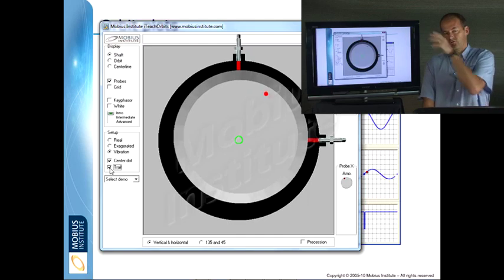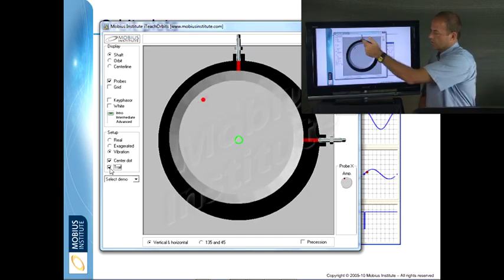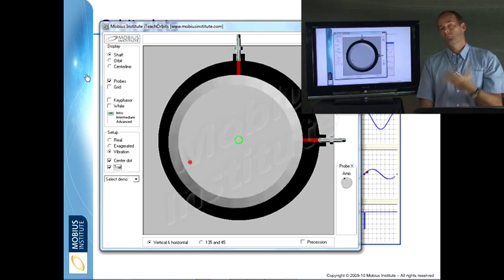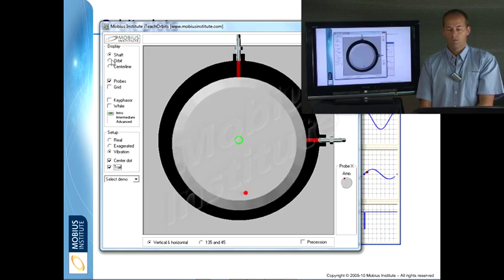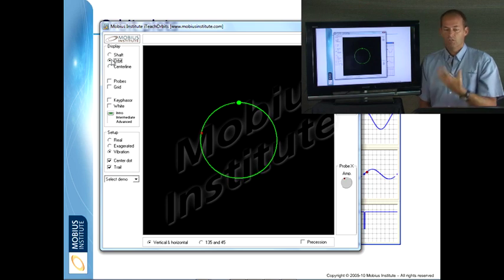So now you can see it has left a trail behind it. And it is showing how the centre of the shaft is moving from one moment to the next. And instead of trying to visualise the centre of the shaft, if we actually use these two dynamic voltage signals and plot them against each other, like X versus Y, we get an orbit plot.